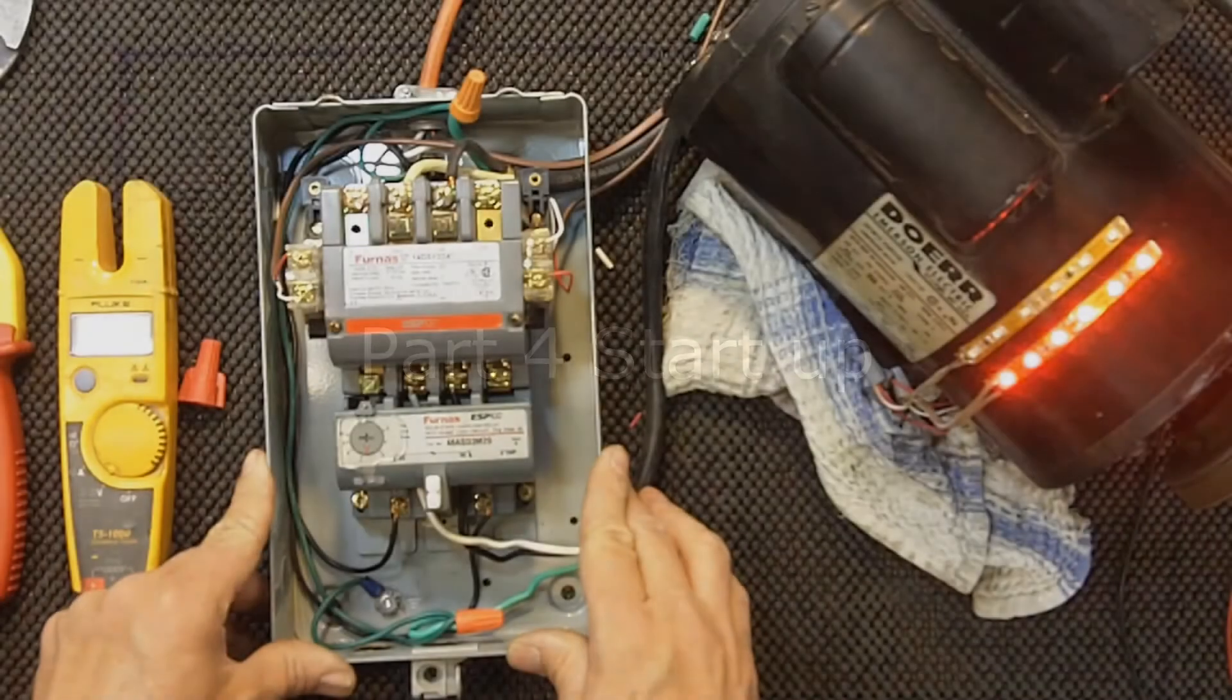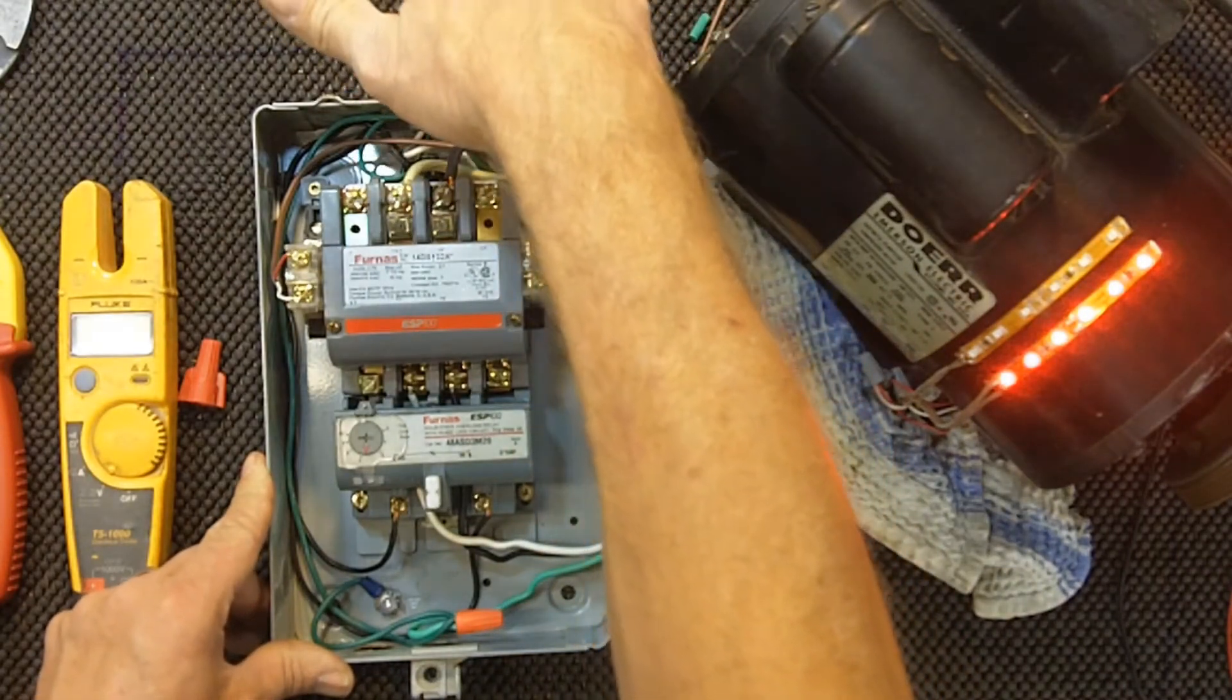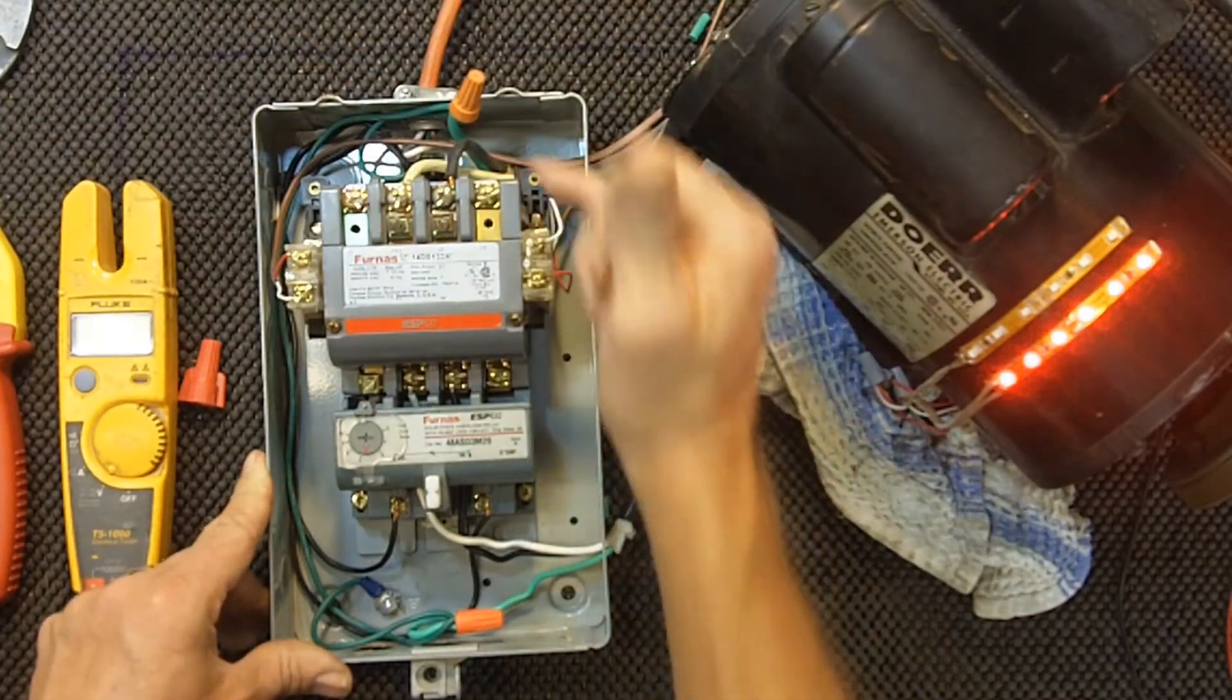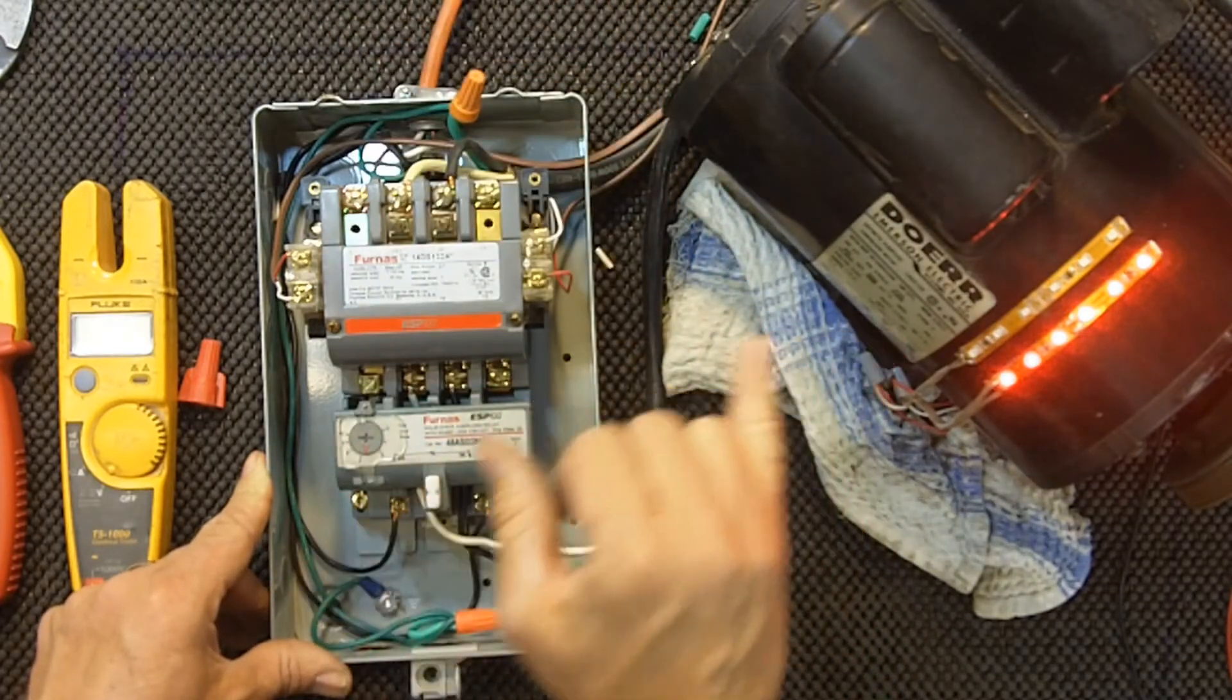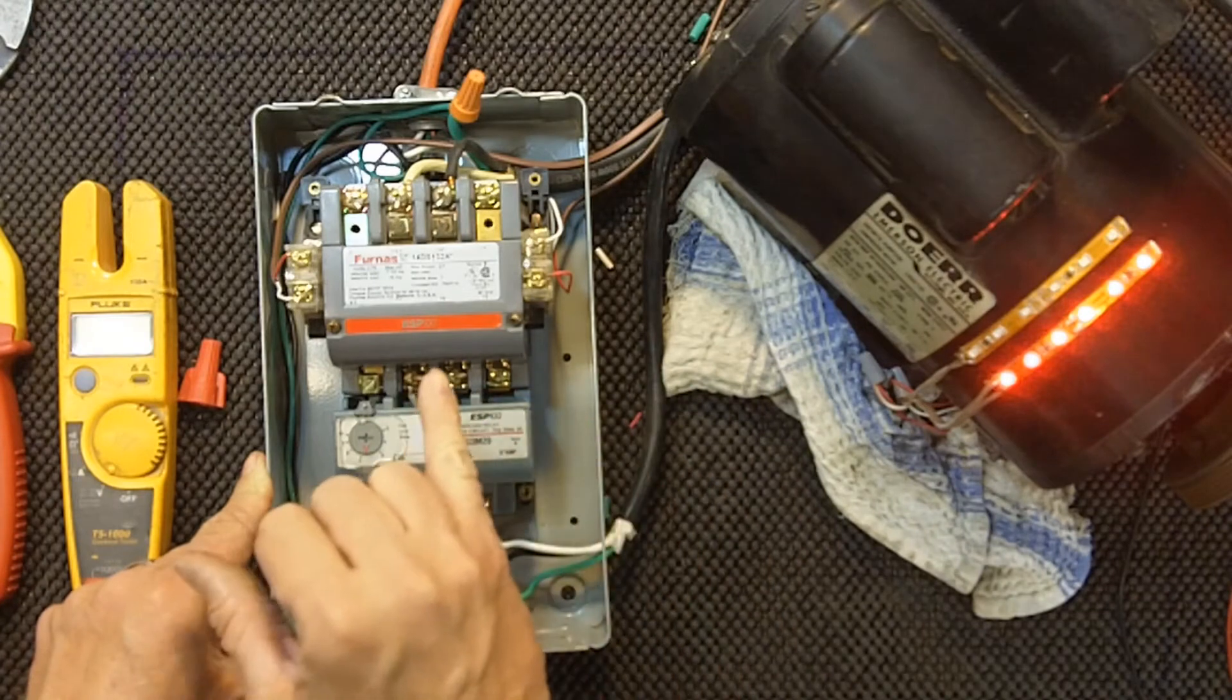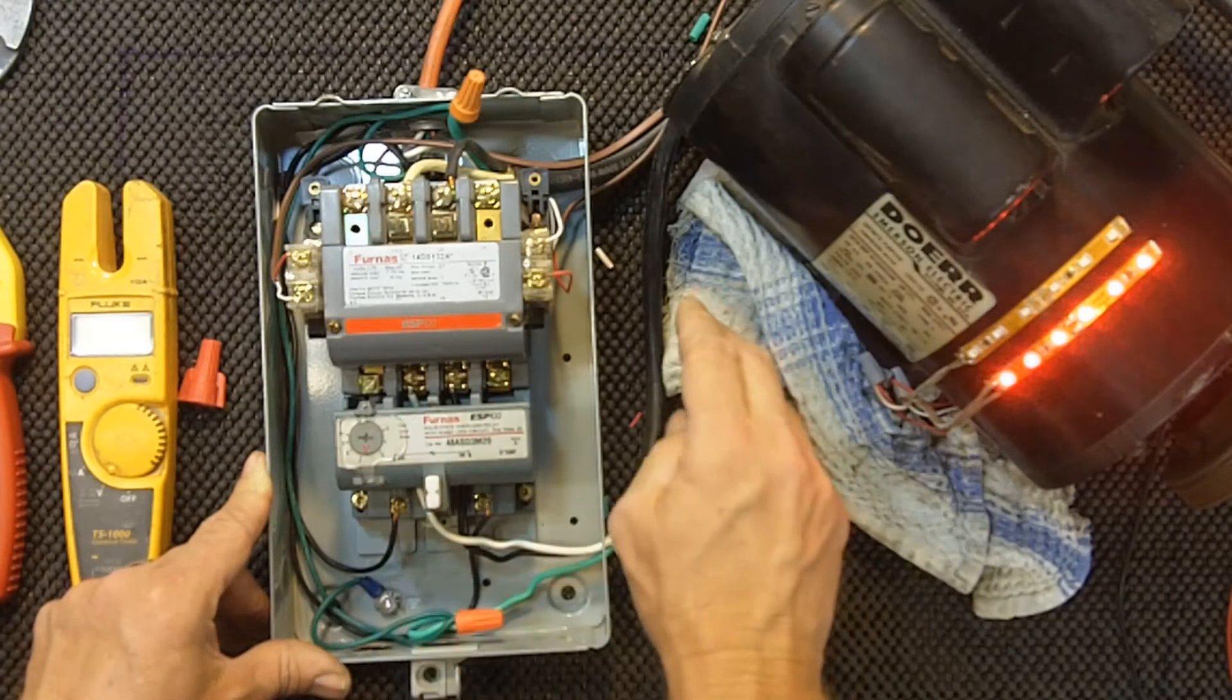I have our contactor wired up here, and I've got my 110 coming in, which is the control voltage for the coil, and then I've got 220 coming in for the motor itself, and it's 220 single phase, and then I've got the load side going back out.